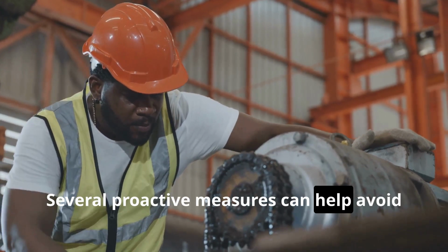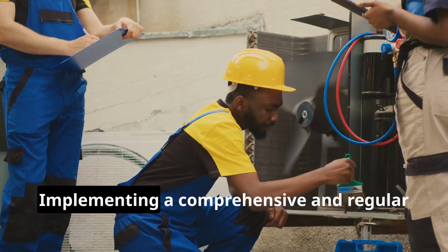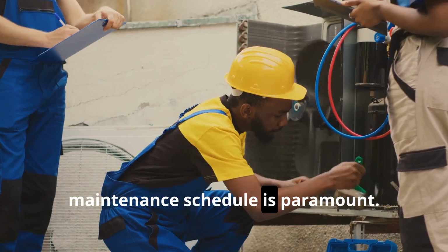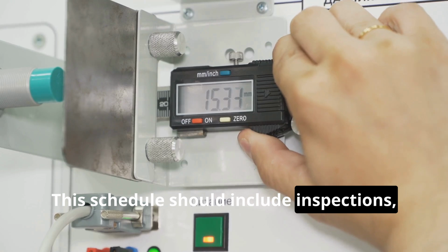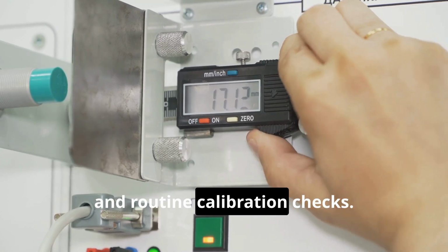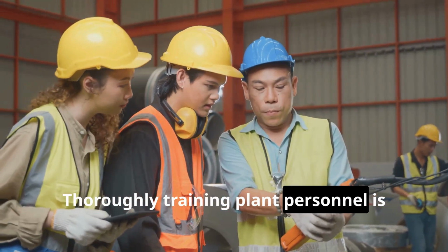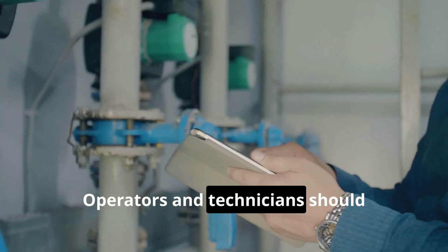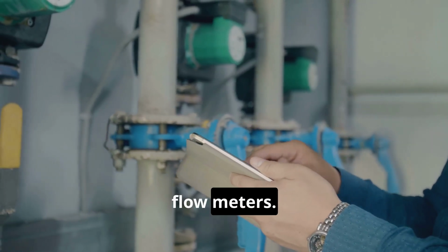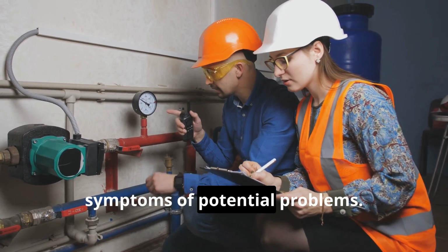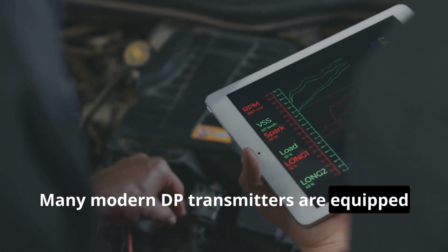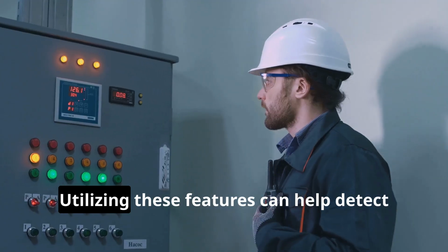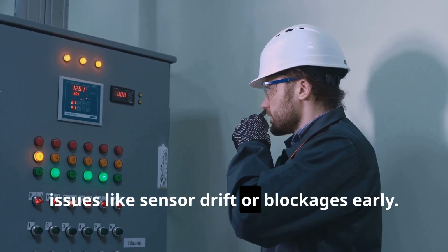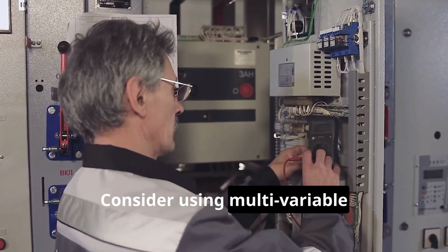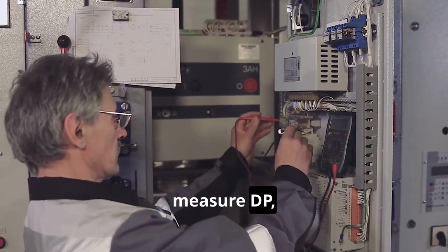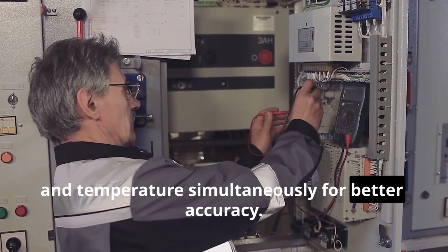Several proactive measures can help avoid these misleading high flow readings. Implementing a comprehensive and regular maintenance schedule is paramount. This schedule should include inspections, cleaning of primary elements, and routine calibration checks. Thoroughly training plant personnel is also crucial. Operators and technicians should understand the operating principles of DP flow meters. They need to be able to recognize symptoms of potential problems. Many modern DP transmitters are equipped with advanced diagnostic features. Utilizing these features can help detect issues like sensor drift or blockages early. Consider using multivariable transmitters where appropriate. These measure DP, static pressure, and temperature simultaneously for better accuracy.